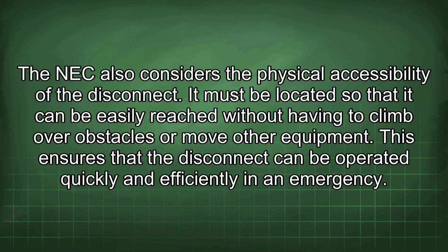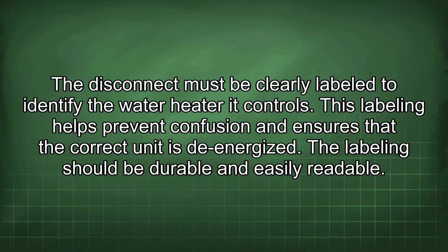The NEC also considers the physical accessibility of the disconnect. It must be located so that it can be easily reached without having to climb over obstacles or move other equipment. This ensures that the disconnect can be operated quickly and efficiently in an emergency. The disconnect must be clearly labeled to identify the water heater it controls. This labeling helps prevent confusion and ensures that the correct unit is de-energized. The labeling should be durable and easily readable.